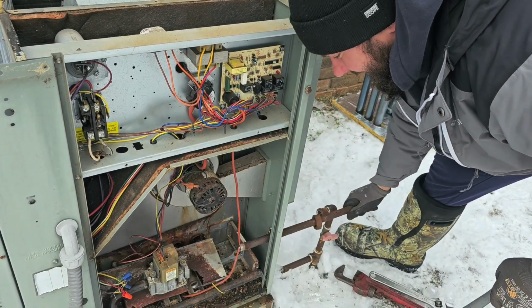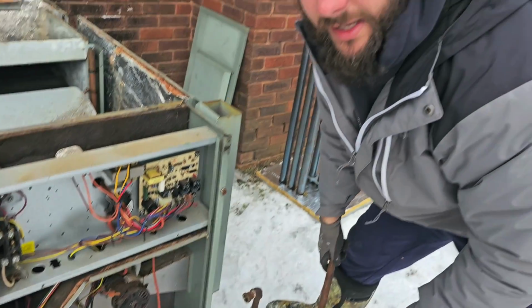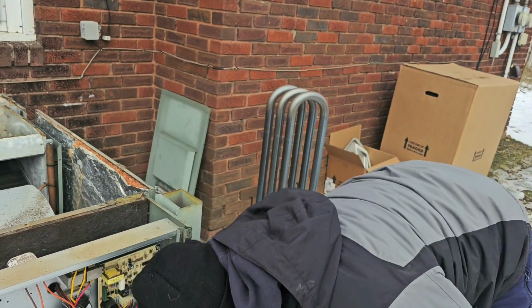But my advice, order everything for the heat side, because chances are the unit you're replacing the heat exchanger on is really old, and you don't want to have any callbacks. So what I do for the customer is I say, I'm going to get you a price on everything for your heat side of your packaged gas unit. And then you can get them a price on a unit. It depends on their budget and what they want to choose to do. But this one, they wanted to go with the heat exchanger.